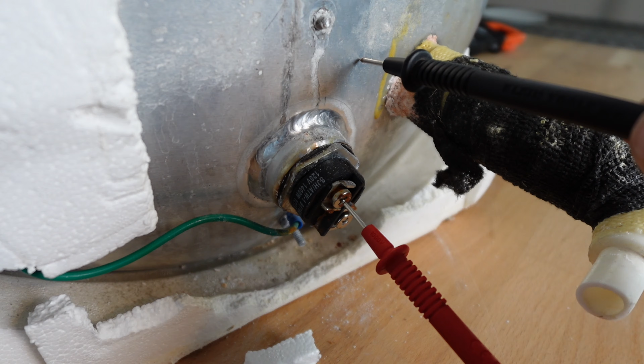So to test the heating element, just give the box a once over, make sure all the wire nuts look good and tight and that nothing came off while you were taking the black box off. If everything looks good, go ahead and throw that breaker for the water heater back on. And then we're gonna take our red probe and put it on one of these two screws on the water heater and take our black probe and put it somewhere on the tank.